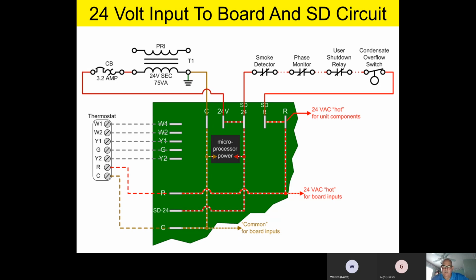Now, this is called the smoke detector circuit, but from a generic standpoint, that SDR and SD24 circuitry is really your safety circuit. So you can remove that jumper in the field, and you can put any sort of dry relay alarm contacts between SD24 and SDR. You could have a phase monitor, a smoke detector.